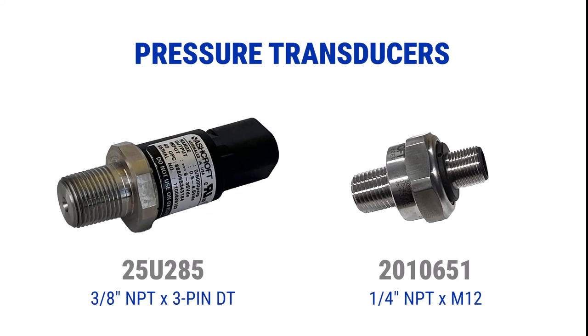Transducers are generally smaller than switches because they have no place for mechanical adjustments to their settings. If your pump is displaying inaccurate pressure levels, then you need to verify that the G3 Max is programmed for the correct settings for your transducer.